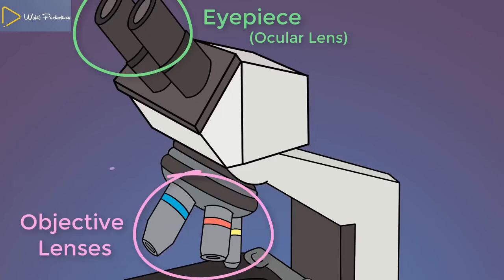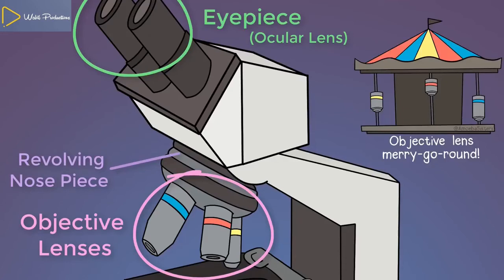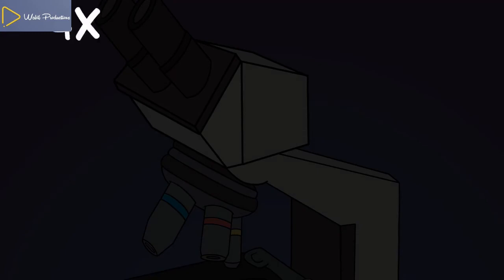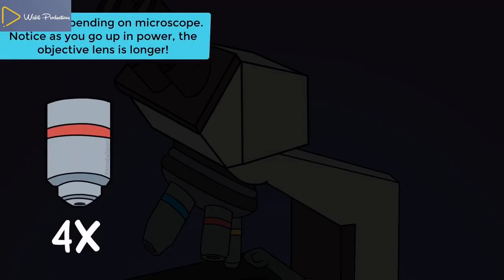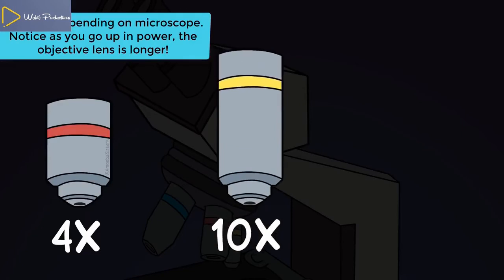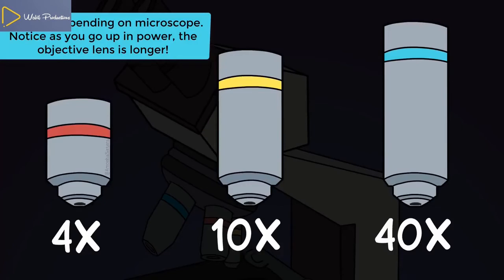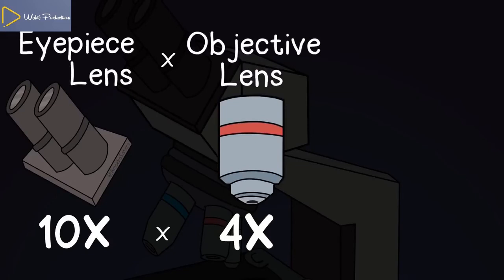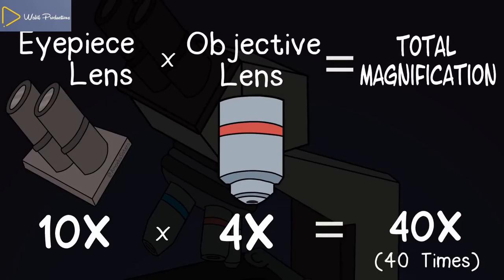The objective lenses are attached to this revolving nosepiece, which allows them to be rotated so you can select the one you want to use. With my particular microscope, I have three objective lenses: a scanning objective lens that magnifies four times, the low power objective lens that magnifies ten times, and the high power objective lens which magnifies forty times. Don't forget the eyepiece lens, because that also magnifies images — my eyepiece lens magnifies ten times. So if I used the scanning objective lens, I would multiply that by the eyepiece lens magnification, giving a total magnification of forty times.